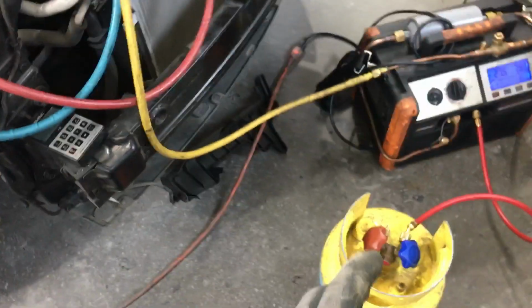Let's say I only take 200 or 300 grams. That means that compressor has been overheating for a long time. That means I charge it up and then the next day it burns up. Well, I need to photograph and evidence that this system comes out low, if it's low, or if it has a full charge, and be very specific on the oil that gets returned.